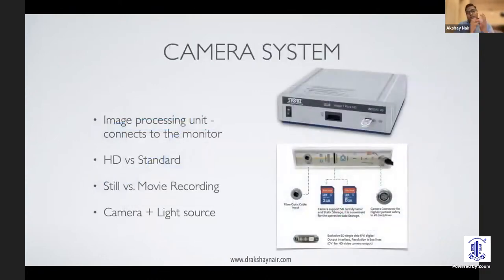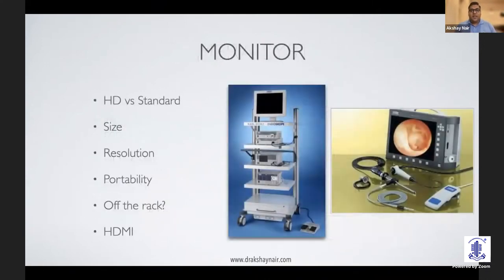Now you've got the endoscope with your camera head, your fiber optic cable with a light source. All of this, especially your camera head wire, goes into the camera system, which is basically the image processing unit, which connects and shows up what you see on the endoscope on the large screen. It can either be an HD or a standard processing unit. Some of them allow you to only record still images. Some of them allow you to record movies. Sometimes you can get a combined unit; the standard companies allow both a camera unit as well as a light source combined into one. Some of them offer you separate units, so you are able to customize them.